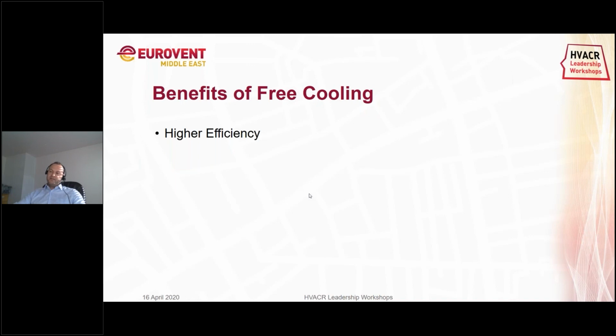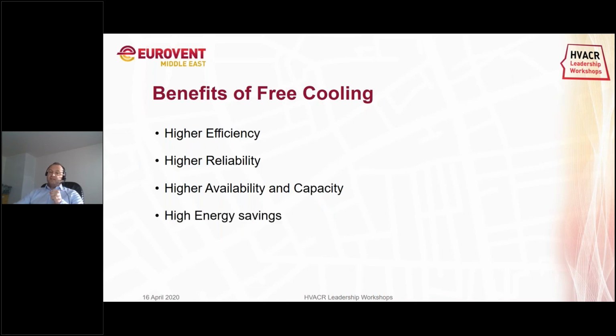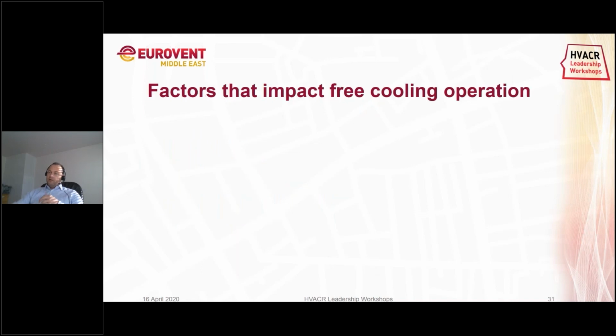is a minimized use of your compressors. There is also a higher reliability as the compressor lifetime increases. And there is a higher availability and capacity as you have a double cooling source. You have cooling with your cooling towers in case there is a chiller breakdown. And last but not least, there are high energy savings as there is a reduction in chiller energy consumption. And this is probably the most important remark that we can give and the most important benefit with regards to free cooling. When you look to the factors that can impact the free cooling, first there is the geographic location.